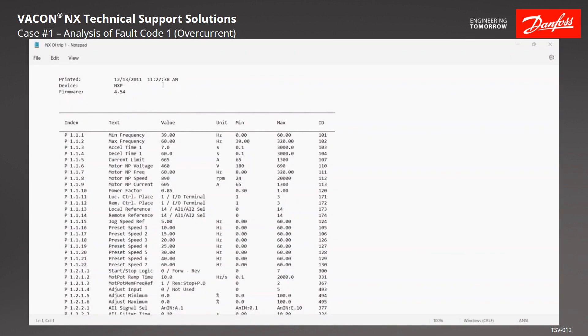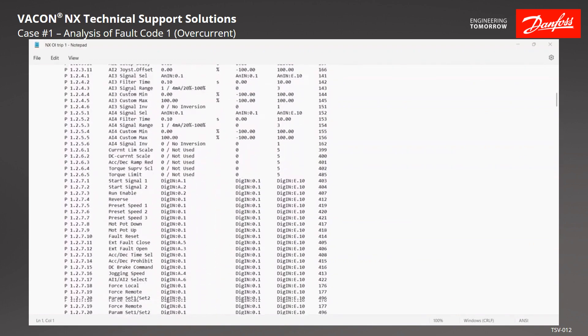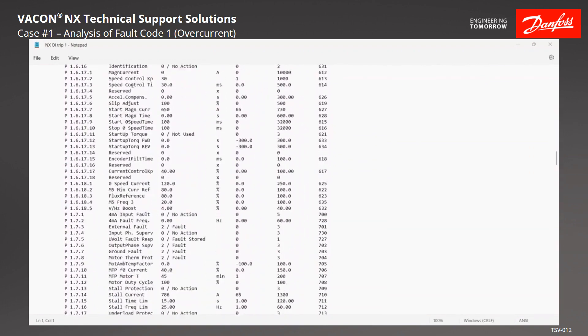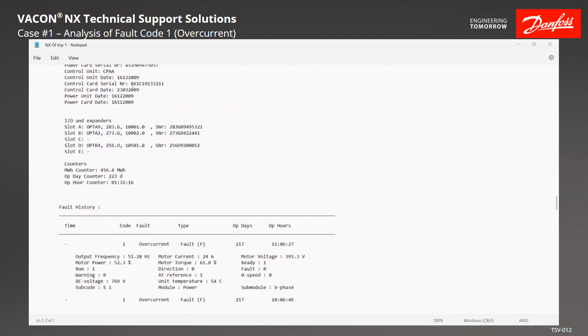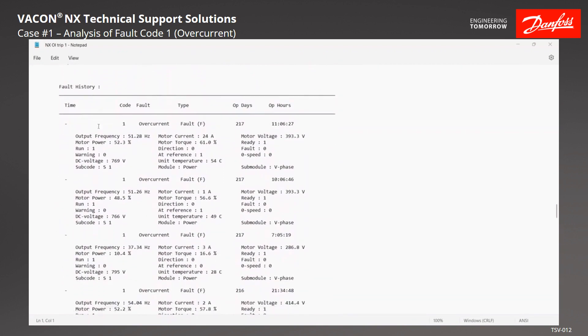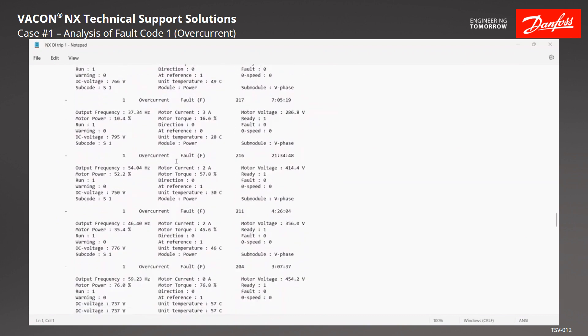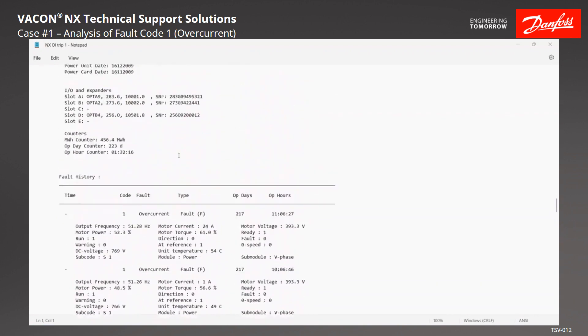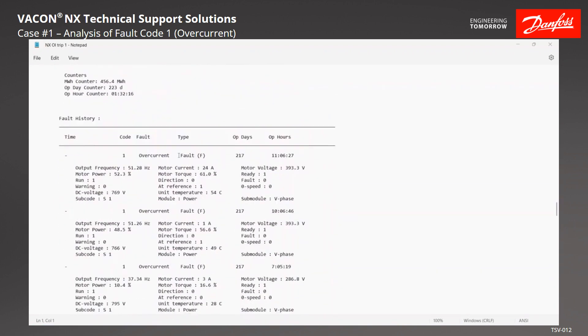Here I have a service file opened up from a customer out in the field. We did remove some of the data so that we aren't showing the serial numbers of a customer's drive. As we go down through this, we're going to look at the fault history to see what faults we're troubleshooting. You can see in fault history we have overcurrent faults — quite a few of them — so overcurrent is probably the fault we're troubleshooting here.